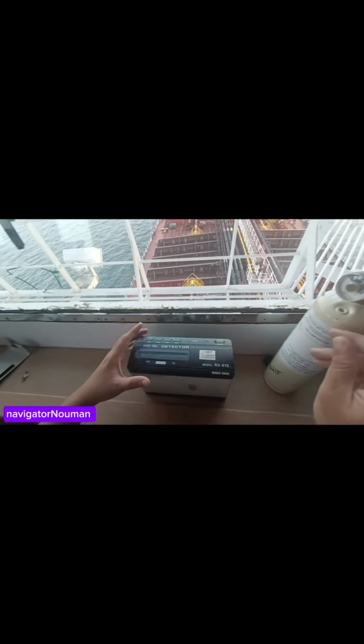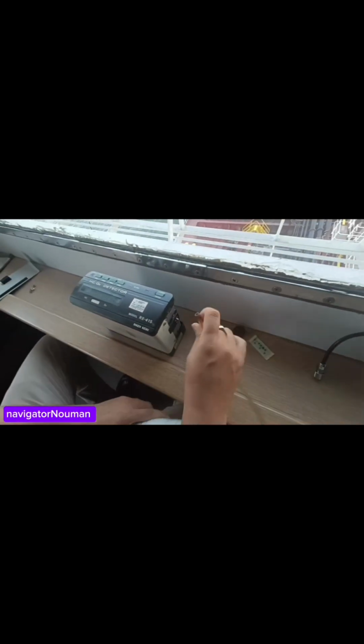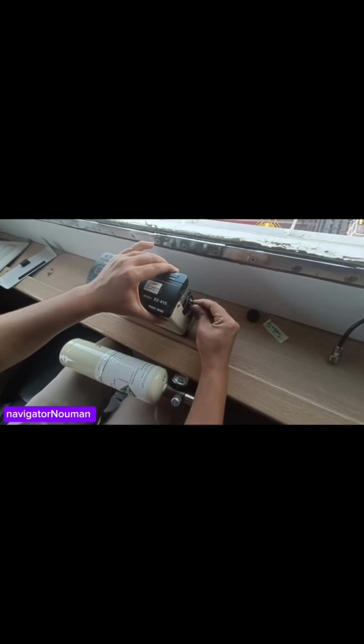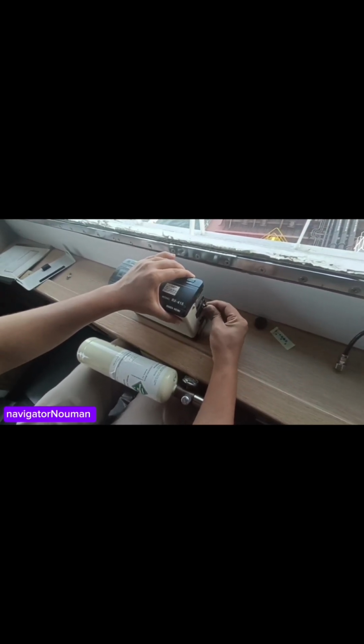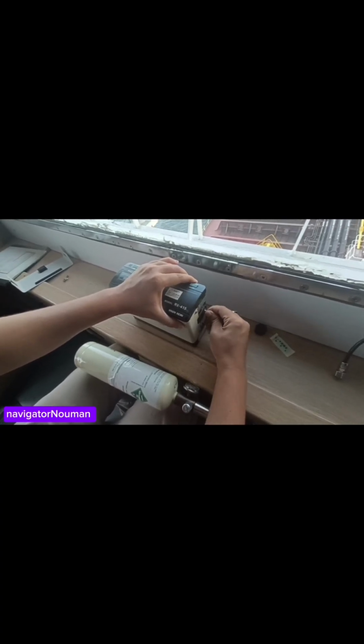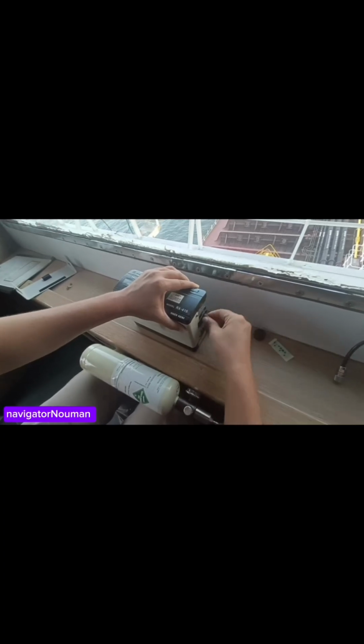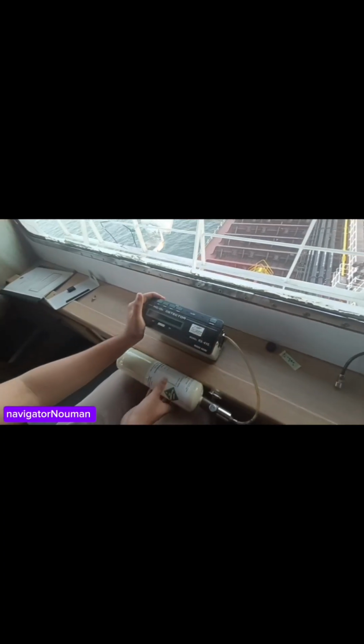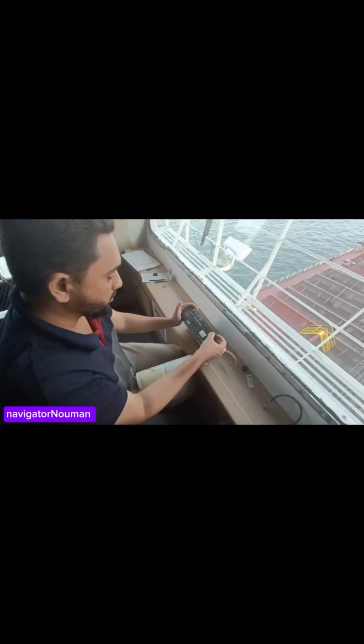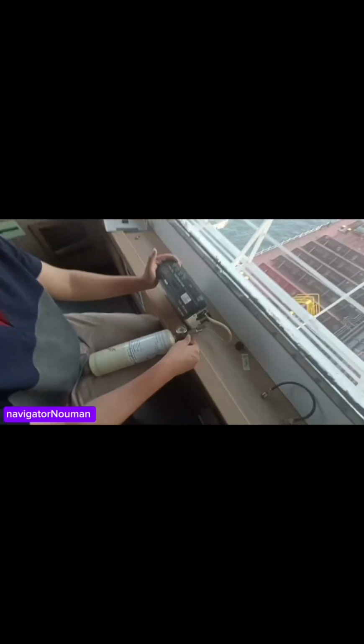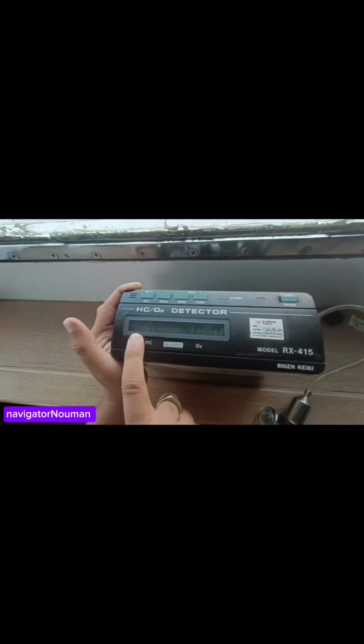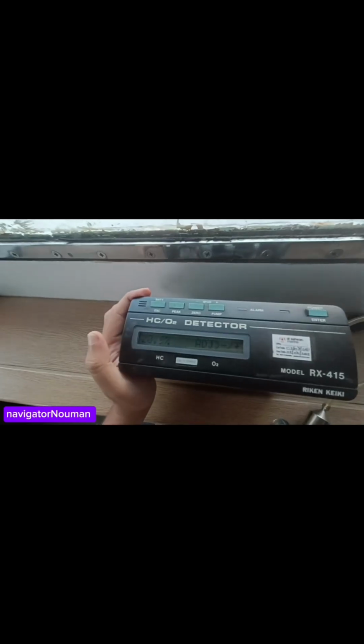Now we will connect the bottle. This is the hose given, so we will connect it here. Now the hose is connected. Now apply gas O2, we will press enter. After that we will open the gas bottle valve. Now the reading is showing 20.9. Once I open the bottle, it will show 0 because nitrogen is 99%, meaning O2 is 0%. Now I'm opening this bottle valve. Once I open, you can see it will come to 0.